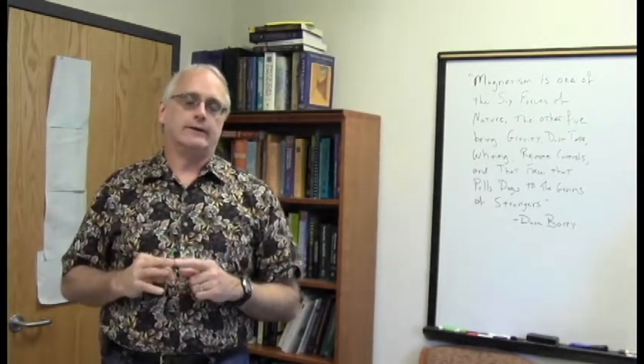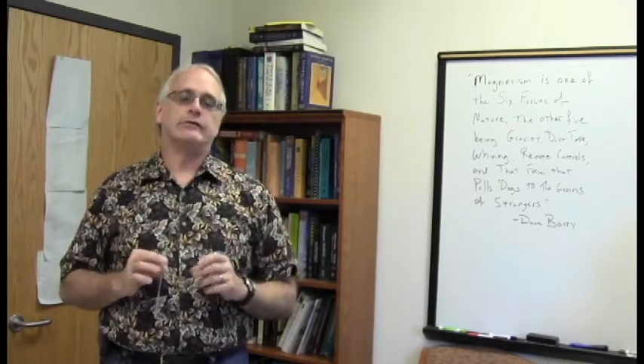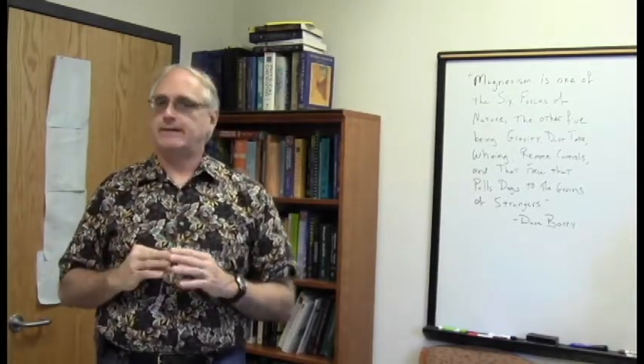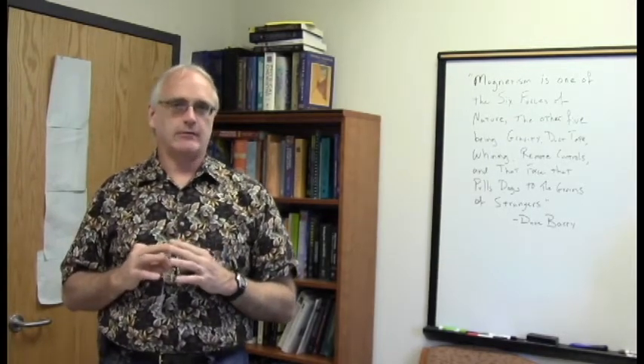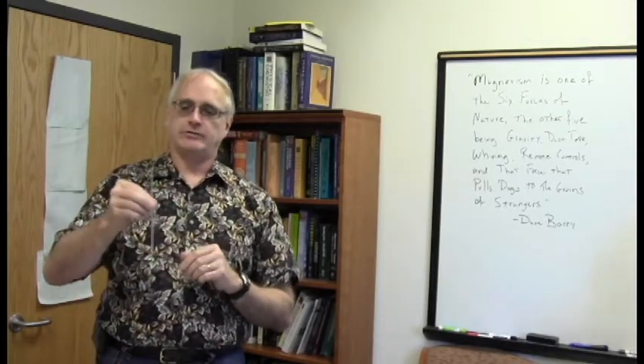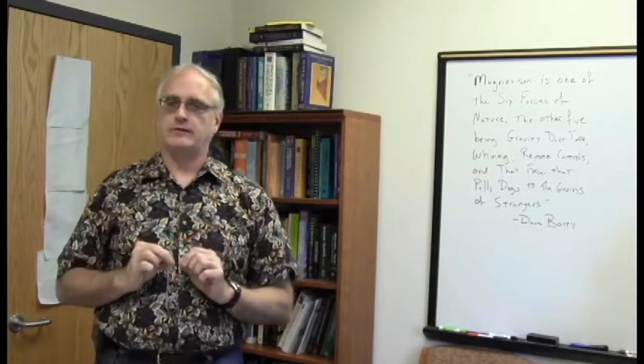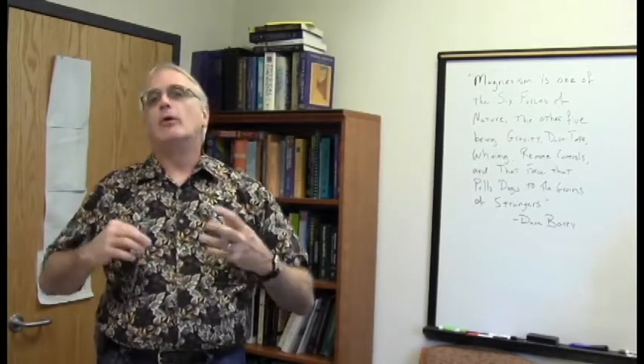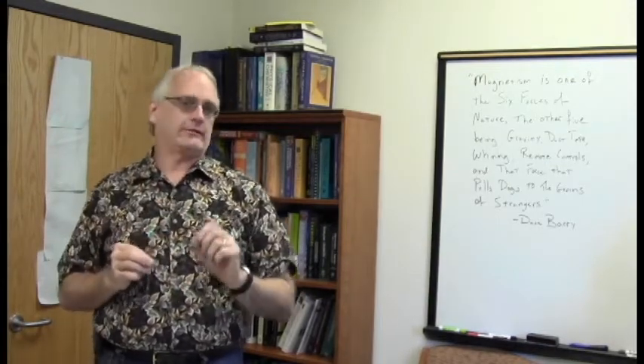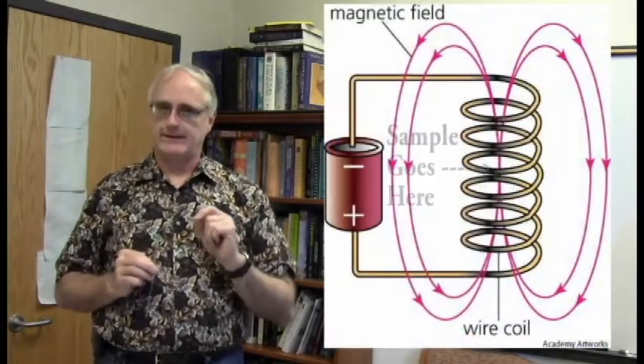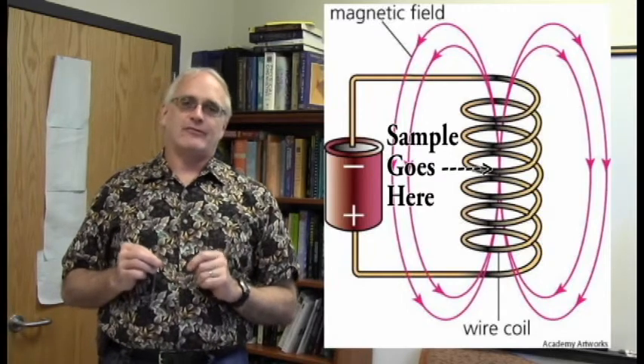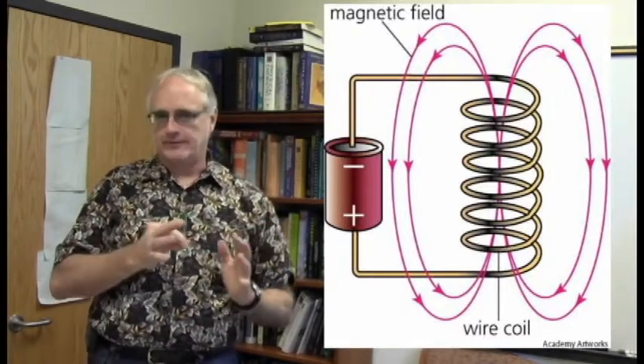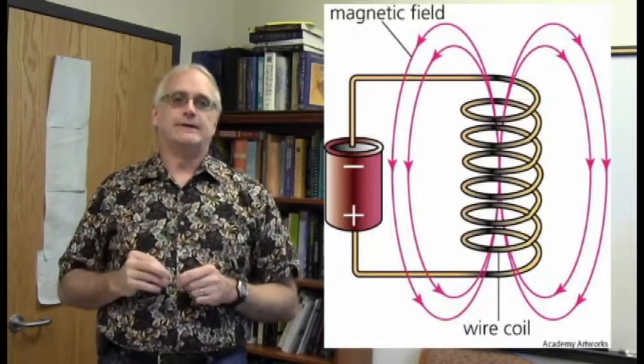One way of getting around that, when the instrument was first installed, one of the jobs of the engineers is to ensure the sample chamber — where the tube ends up deep inside the magnet — is centered perfectly, to less than a micron tolerance, both up and down and left, right, and front to back. It has to be perfectly centered in that magnet. But even with all that effort, the magnetic field running through the tube is still going to be slightly curved. So what we have to do, in order to compensate for differences between sample tubes, is a process called shimming the magnet.